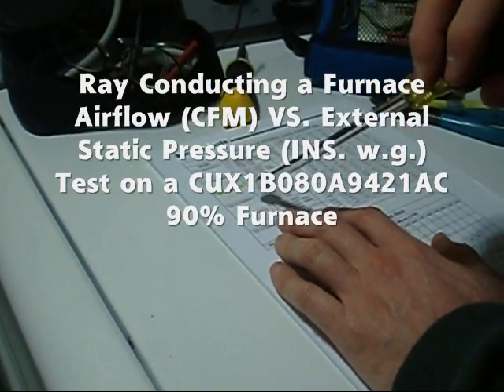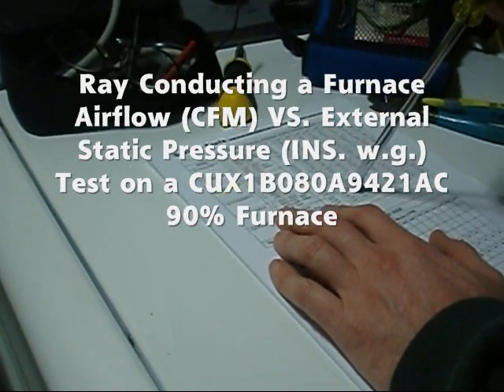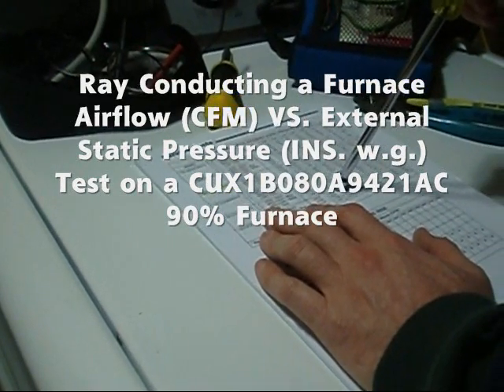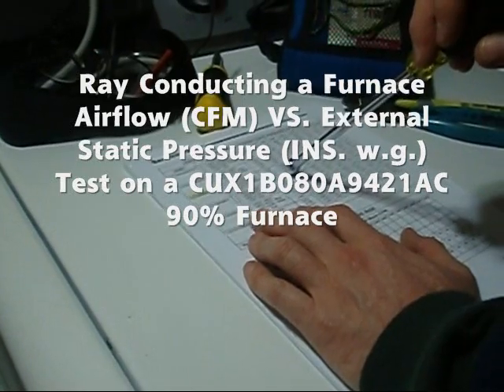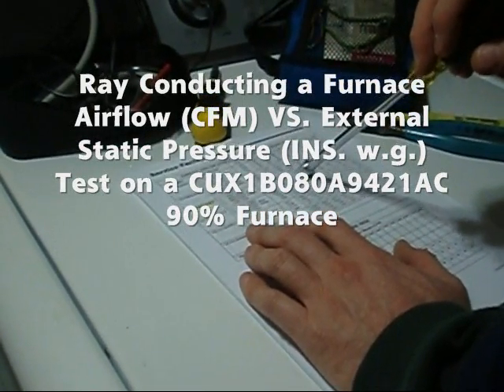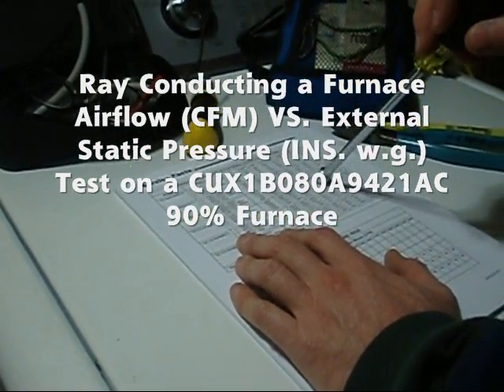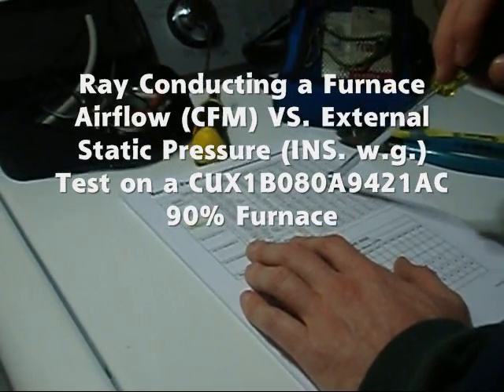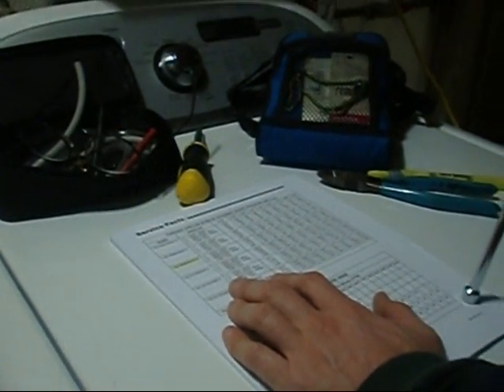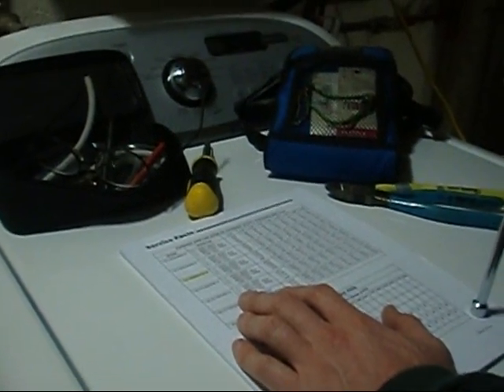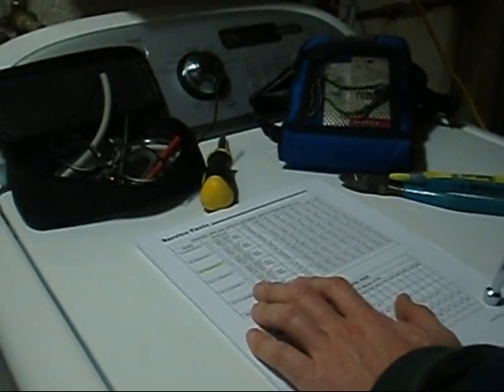I've got your model number highlighted. We're going to run the test in cooling mode on this 2.5 ton American Standard heat pump. So that should be around 1,000 CFM, right? Yeah, it's 400 per ton, so 4 and 8 plus 2 is 1,000. We'll see how close we can get to that with the airflow CFM and external static pressure test.